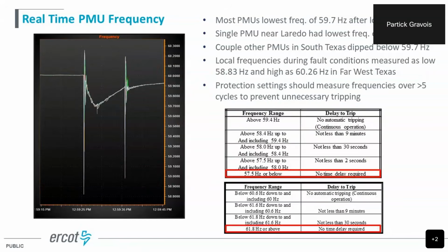Now we have frequency of the real-time PMUs. Again, you're seeing this sharp drop in local frequency. So this is just a couple of PMUs across the system that are seeing this, measuring this quick low frequency. Again, you shouldn't have anything tripping in this period right here. And then we have the frequency due to loss of generation get down to about 59.7. A couple PMUs got a little lower, but for the most part, 59.7 was the lowest, and it recovered pretty quickly. And then you had the reclose event as well.